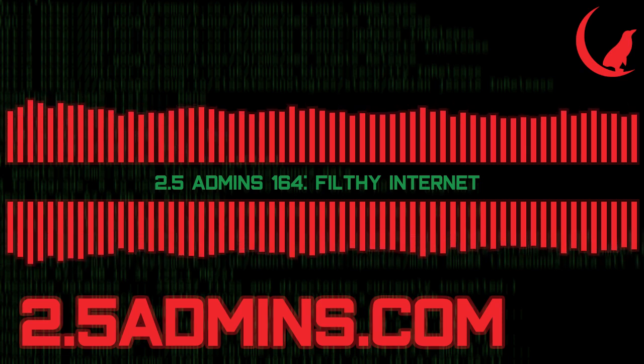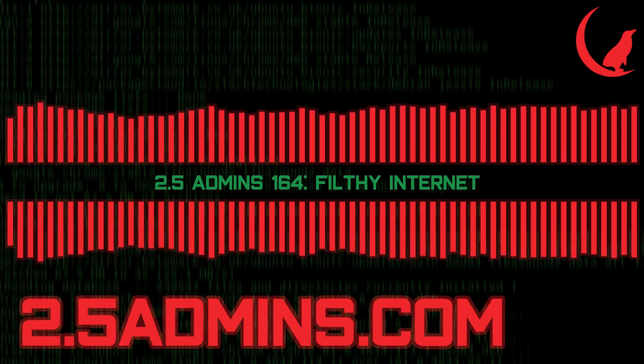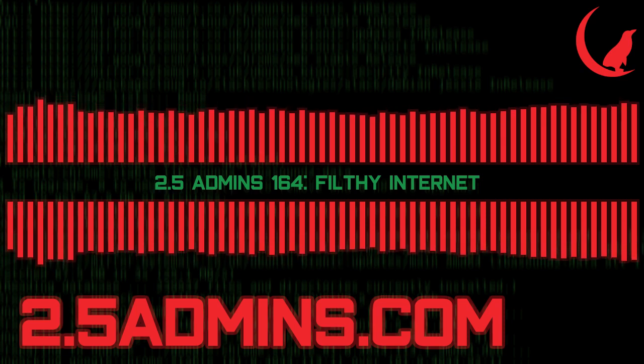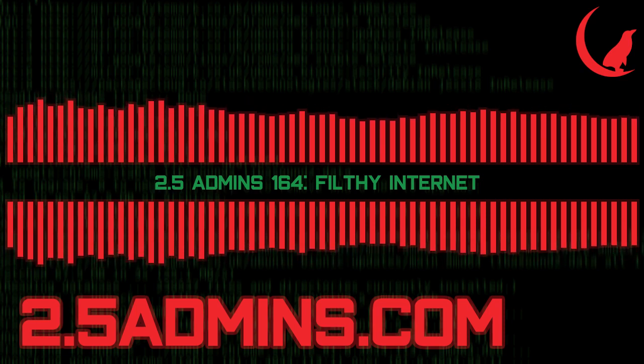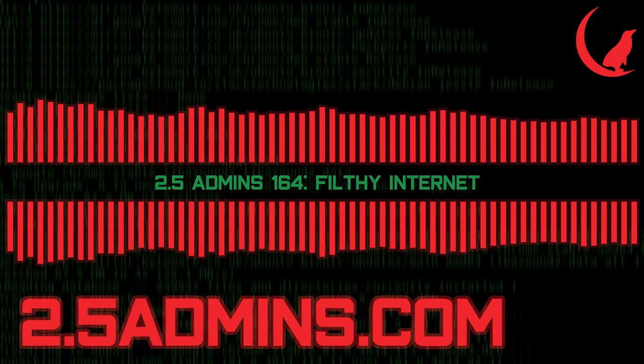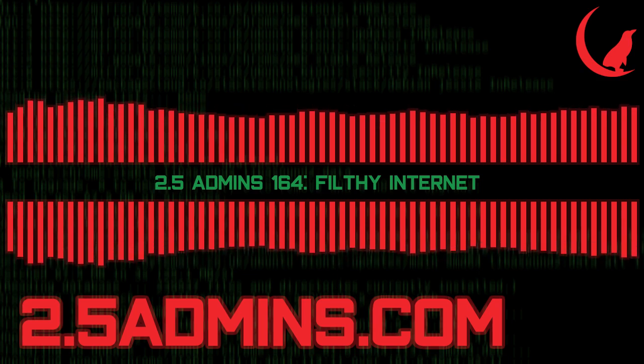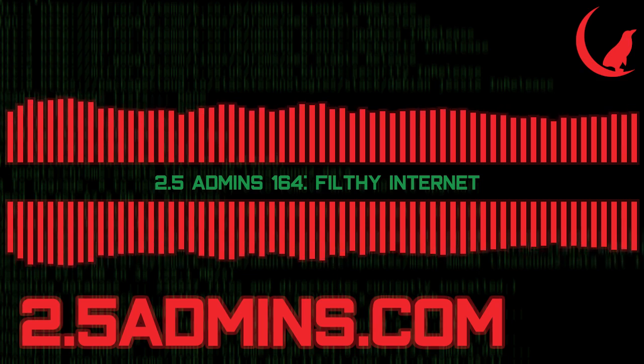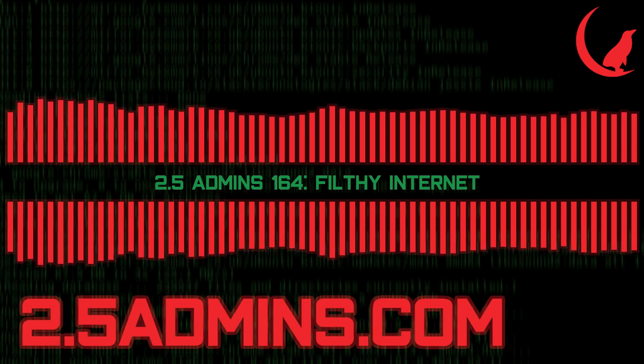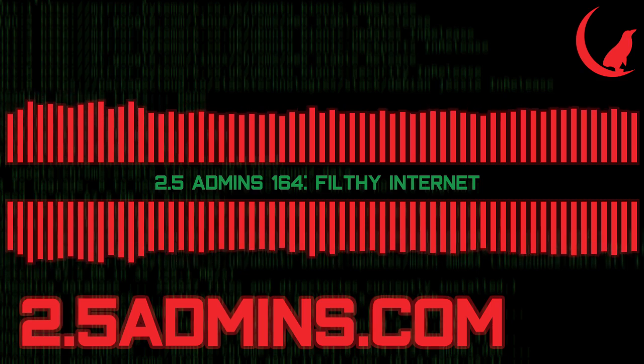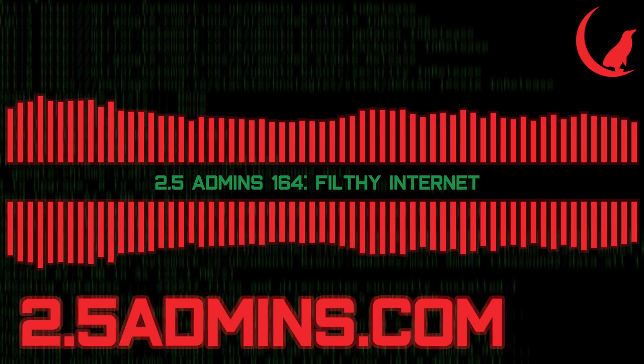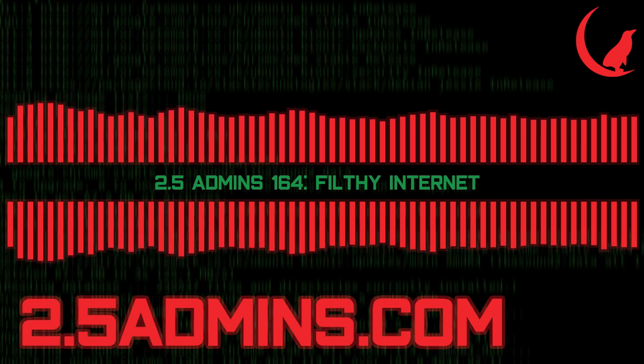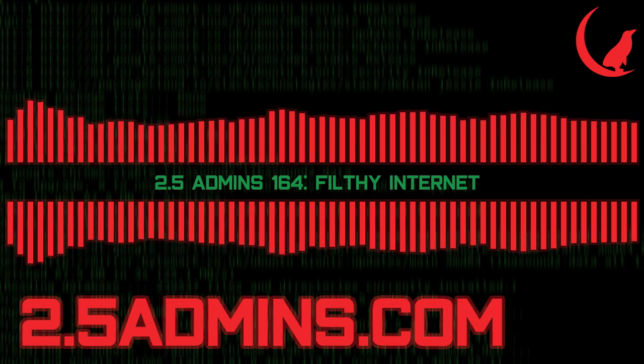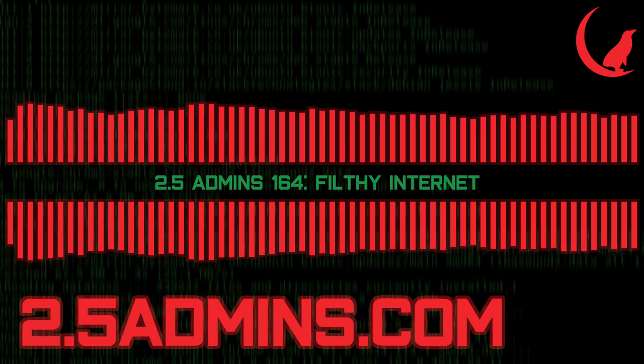Effectively this was kind of what you're describing. The saving grace is that unlike a lot of those accursed closets, this one actually had not only an AC exhaust but an AC return. So it absolutely was climate controlled down to where every other room in the building was - it was not any warmer, it just also wasn't any colder. If you want to get that crazy with the thermals on your rack-mounted equipment, you'd better be at data center ambient temperature, not human office ambient temperature.